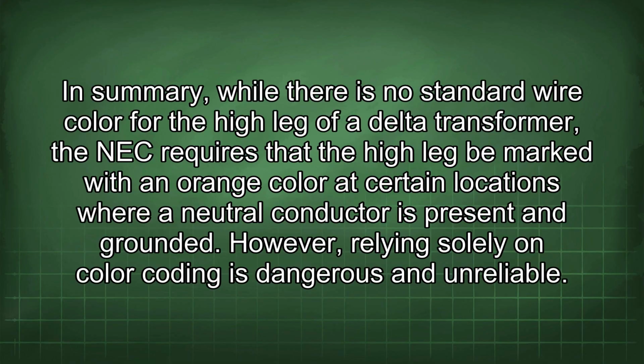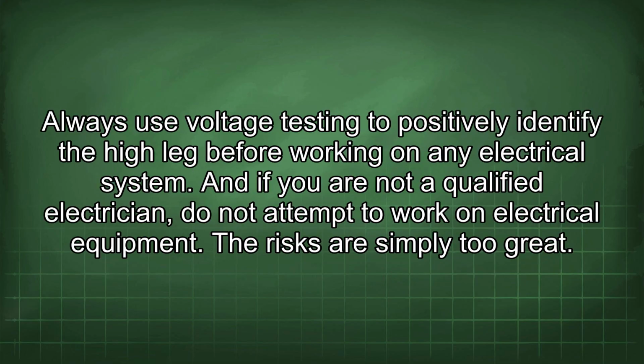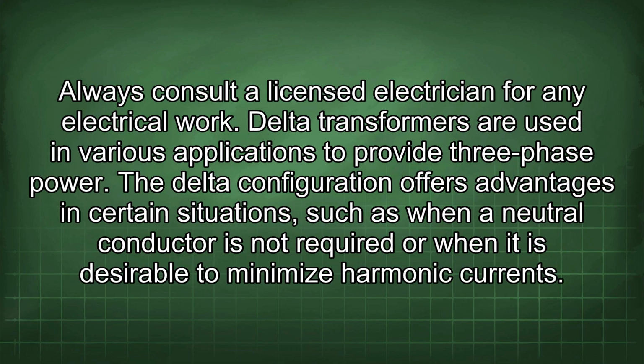In summary, while there is no standard wire color for the high leg of a delta transformer, the NEC requires that the high leg be marked with an orange color at certain locations where a neutral conductor is present and grounded. However, relying solely on color coding is dangerous and unreliable. Always use voltage testing to positively identify the high leg before working on any electrical system. And if you are not a qualified electrician, do not attempt to work on electrical equipment. The risks are simply too great. Always consult a licensed electrician for any electrical work.